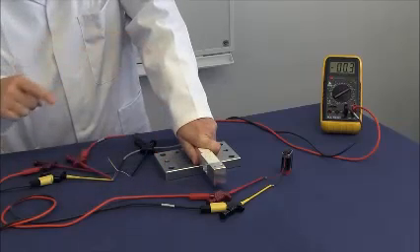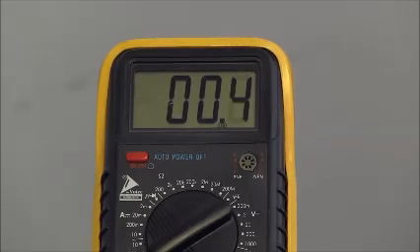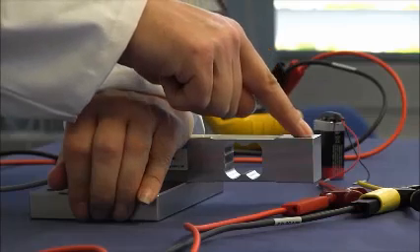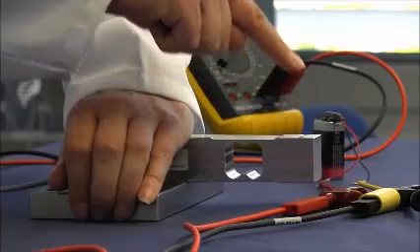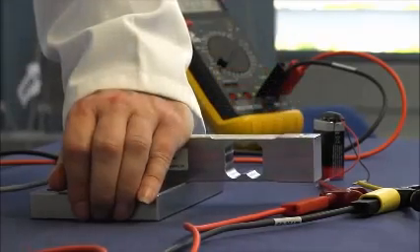The zero-point tolerance is usually 1% of the nominal rated sensitivity. With a measuring range of 200 millivolts, this corresponds to approximately two digits and thus roughly corresponds to the multimeter's accuracy. Hence this approach only allows you to verify whether or not a strain gauge transducer is generally functional.